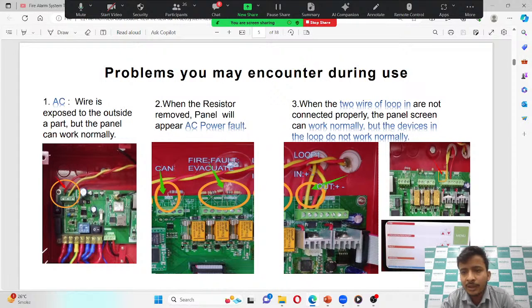When the 2 wires of the loop in are not connected properly, the panel screen can work normally, but the devices in the loop do not work normally. So when you are connecting the loop in and loop out cables of all the devices, the panel may work normally, but the devices connected in that loop give a fault, such as a communication fault or any similar fault. So you must make sure the wires are connected properly, or connect thimbles at the ends of the wires so that they are properly connected with the ports.